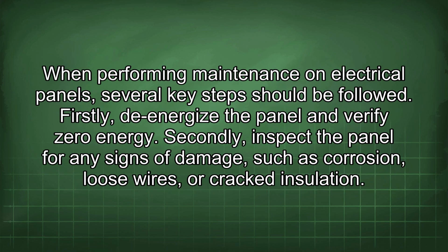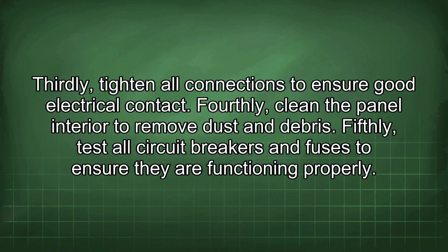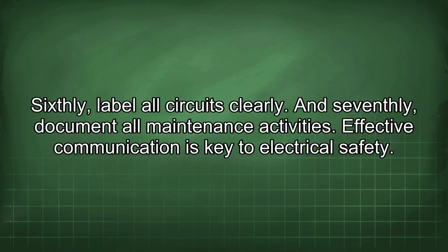When performing maintenance on electrical panels, several key steps should be followed. Firstly, de-energize the panel and verify zero energy. Secondly, inspect the panel for any signs of damage, such as corrosion, loose wires, or cracked insulation. Thirdly, tighten all connections to ensure good electrical contact. Fourthly, clean the panel interior to remove dust and debris. Fifthly, test all circuit breakers and fuses to ensure they are functioning properly. Sixthly, label all circuits clearly. And seventhly, document all maintenance activities.